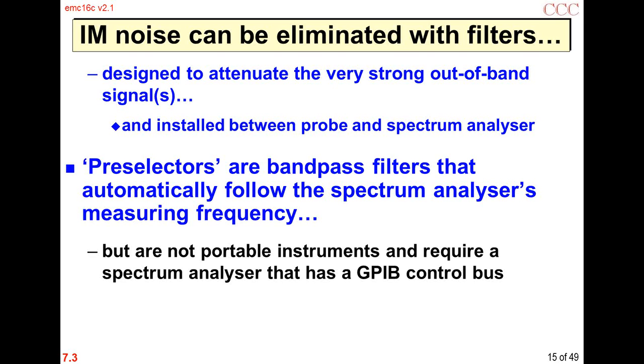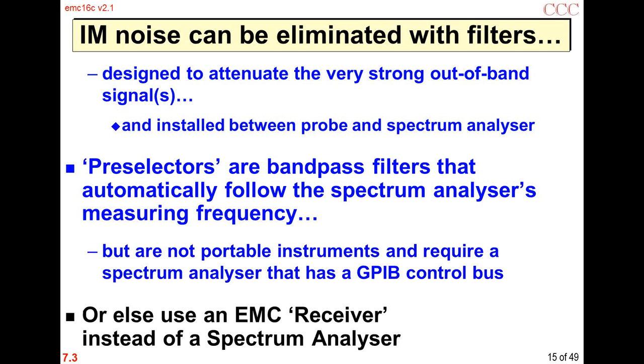Or we might use an EMC receiver instead of a spectrum analyzer. Now, I always use spectrum analyzers because all of the receivers that I've seen, which have a tuned radio frequency stage before the mixer, are rather slow for the kind of diagnostics you do with a spectrum analyzer. So I don't tend to do that. But if you have a receiver handy, you might choose to do that.